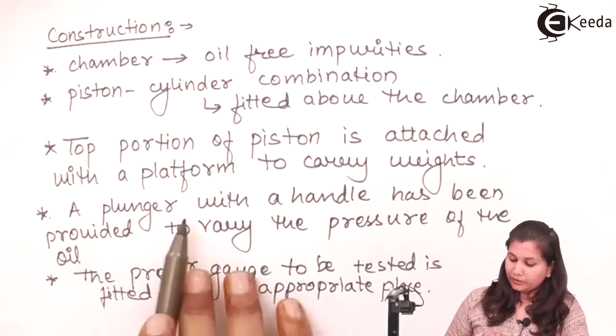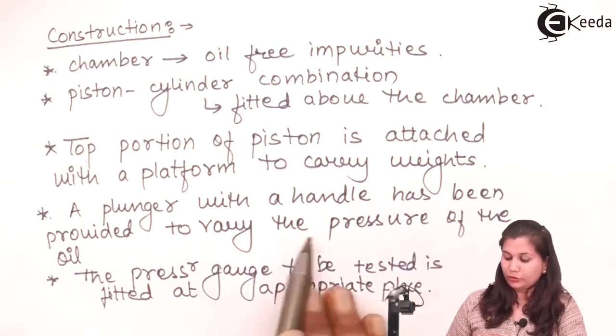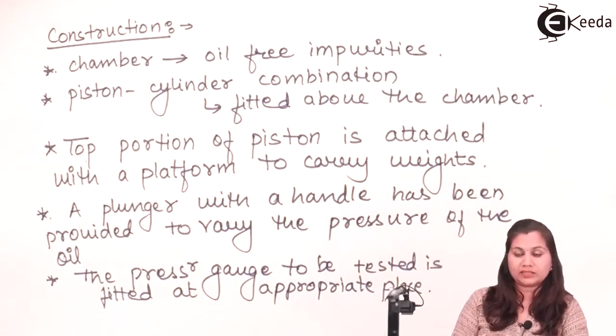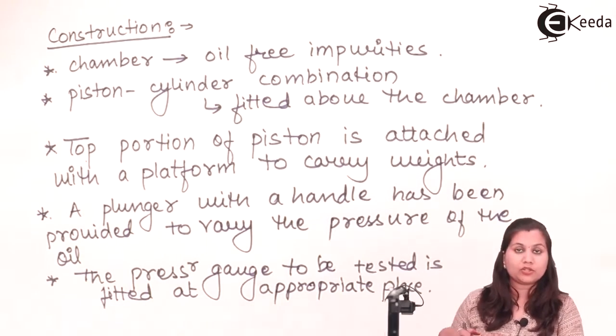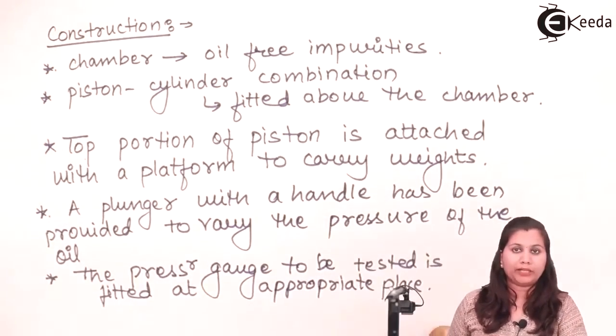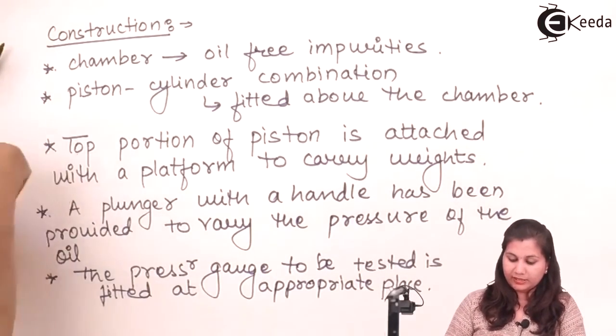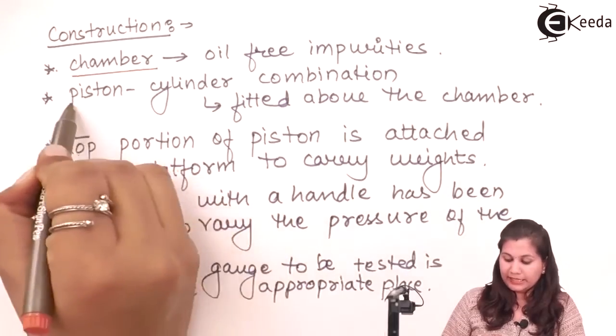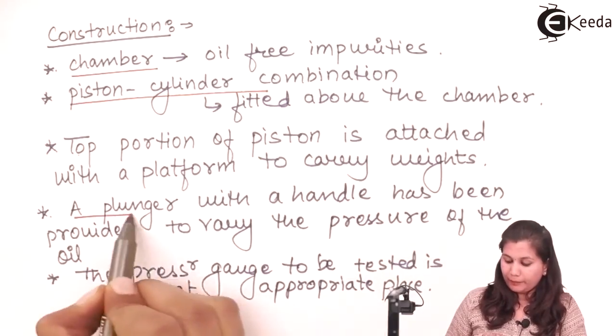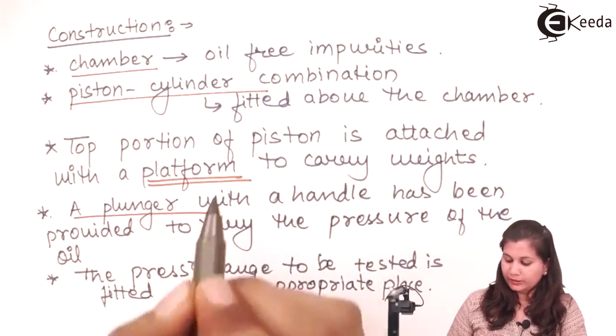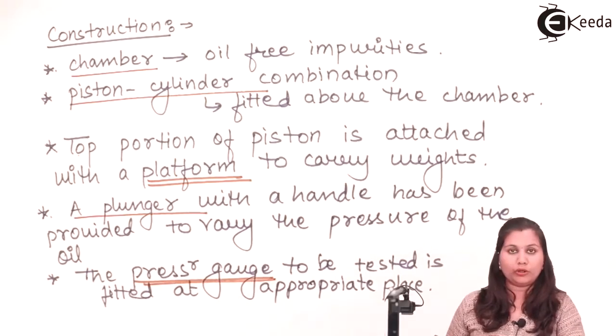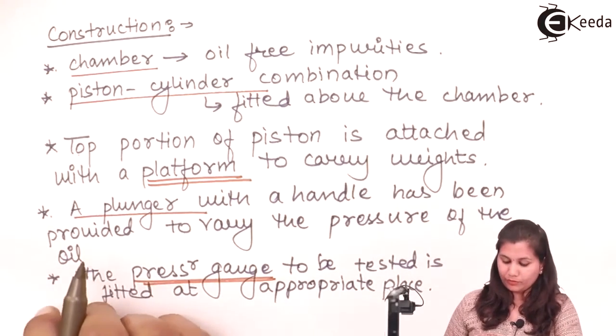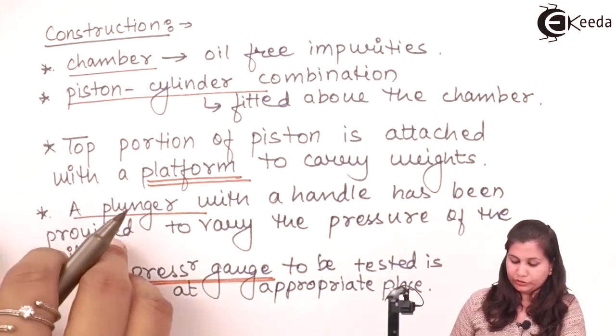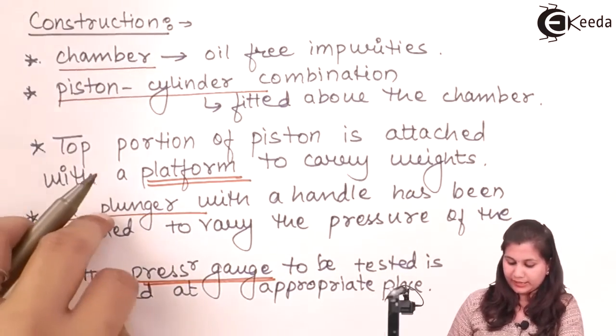A plunger with a handle has been provided to vary the pressure of the oil which is present in the chamber, and the pressure gauge which is to be tested, or the device which we want to calibrate, is fitted at the appropriate place. So in the construction you can see that the deadweight tester consists of the chamber, the piston cylinder combination, then a plunger, a platform, and the pressure gauge which we want to test. Now let's see the diagram for the deadweight tester.